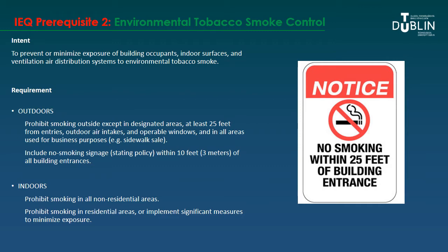The second prerequisite is about avoiding tobacco smoke in buildings. This is a departure from LEED 2009, which allowed smoking in commercial buildings if the room was separately ventilated. LEED version 4 is the first version that actually prohibits smoking inside non-residential buildings. Outdoors, smoking must be prohibited except in a designated area at least 25 feet from entries, air intakes, or operable windows, and no-smoking signage is required within 10 feet of all entrances.